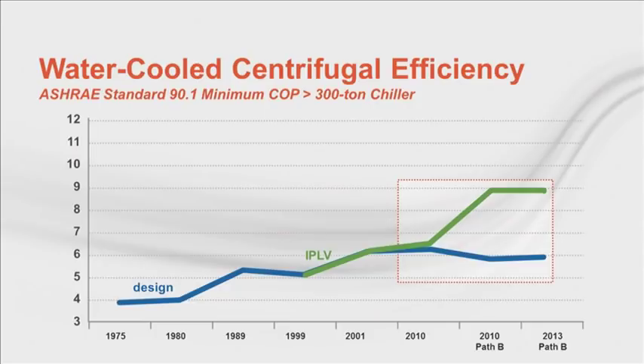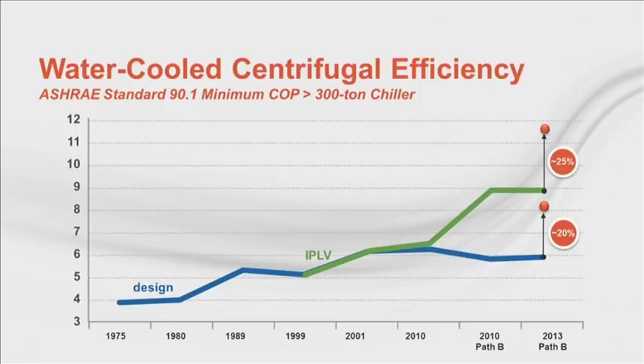But there are more efficient chillers that can be selected. The dots represent data from premium efficiency chillers. In other words, ones selected for very high full load performance and others selected to achieve a high IPLV. So what does this all tell us? Simply put, there remains additional chiller efficiency levels to design into chiller plants. In fact, over 20% higher full load and 25% higher part load efficiency.